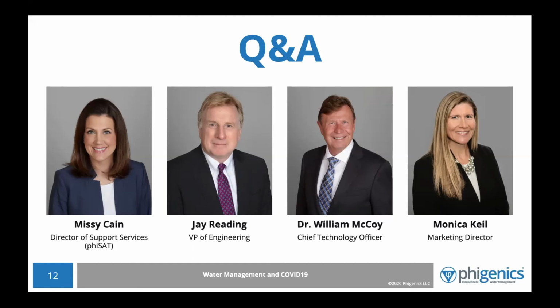Thanks for that question. It's right to the point, and the answer relates directly back to the points that Jay made, especially for the low occupancy type buildings. The most concise way to describe it is to reduce water age in the potable water system of the building and make sure the disinfectant concentrations are in spec or high enough. Those are the two main measures that can be made, and I take the question to refer to control measures.